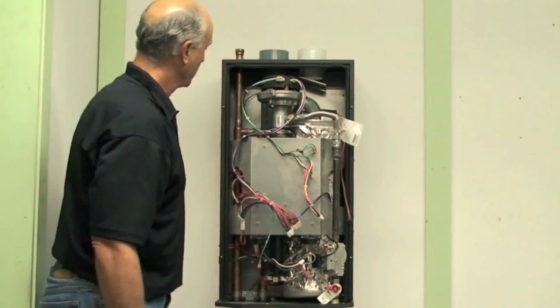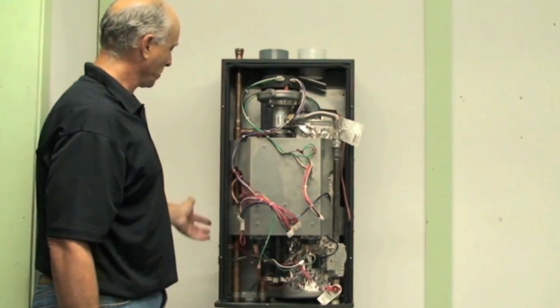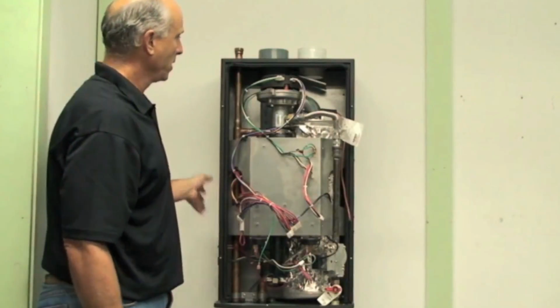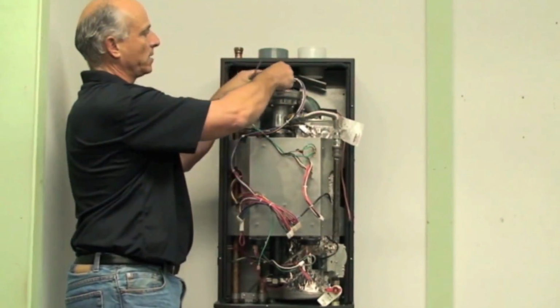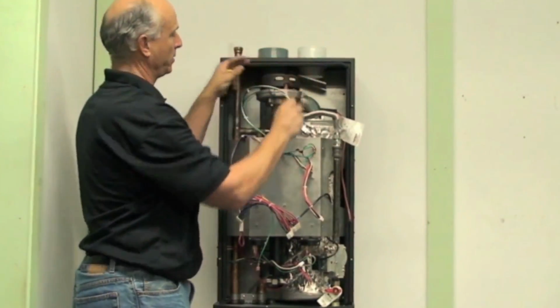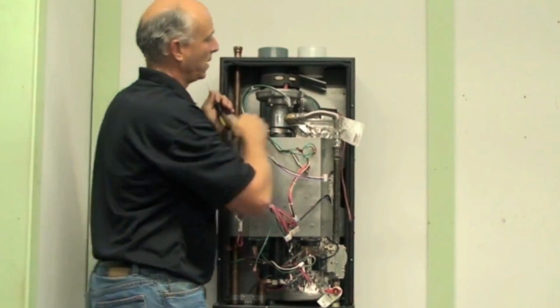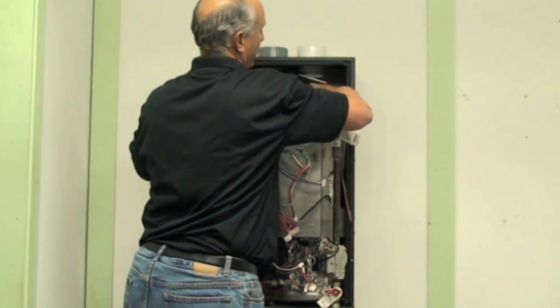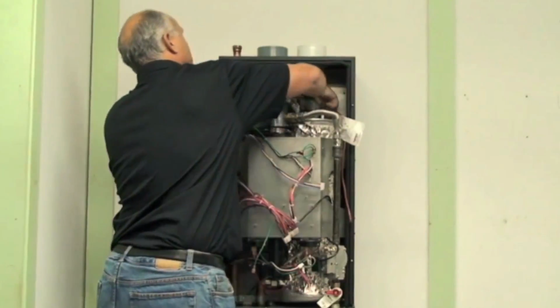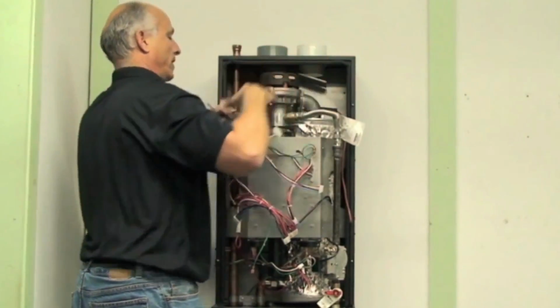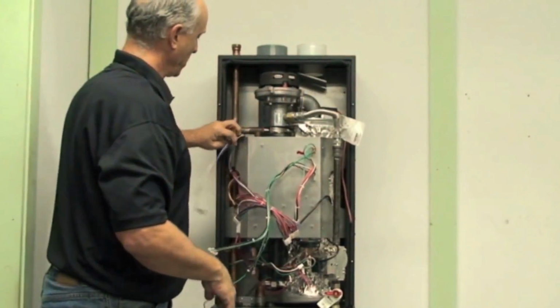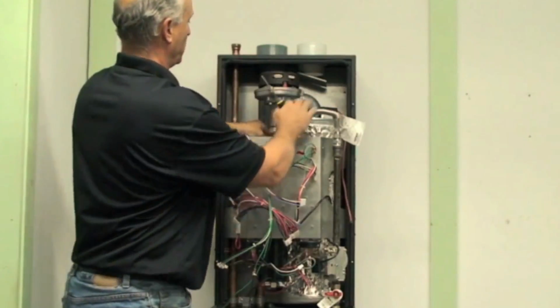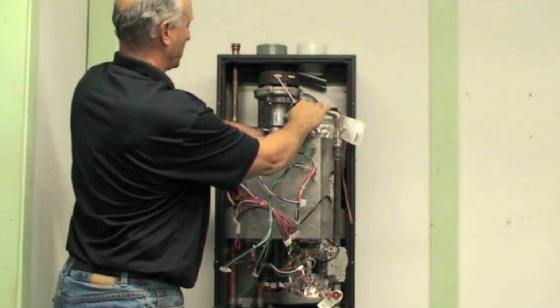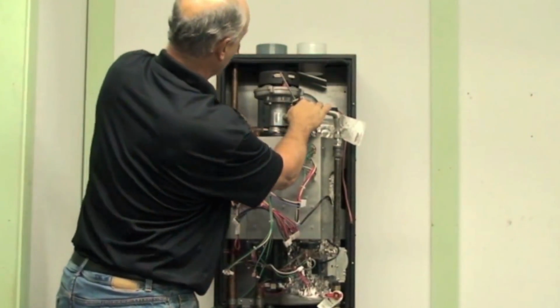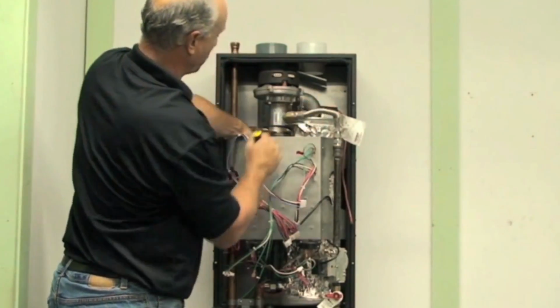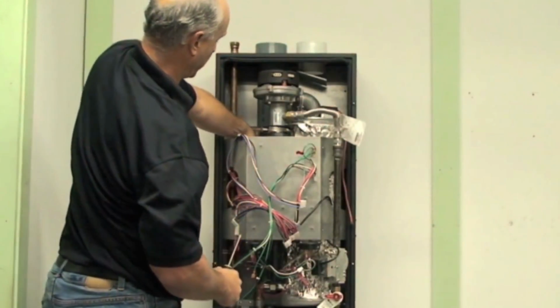the control board. There's a couple of screws on both sides of the unit, and that'll give you complete access. I'll also take the fan and I'll disconnect that too at the same time. And I'm going to disconnect my ground leads and my rectifier. So now I've got all those disconnected. There's some components, the water switch I'm going to disconnect. I'm also going to disconnect my Molex for my high limit and operating limit.